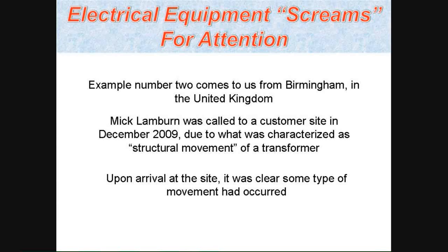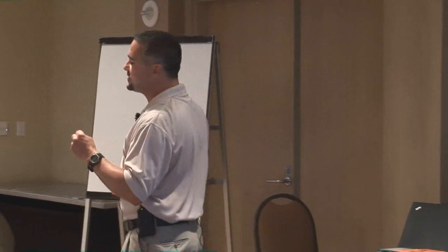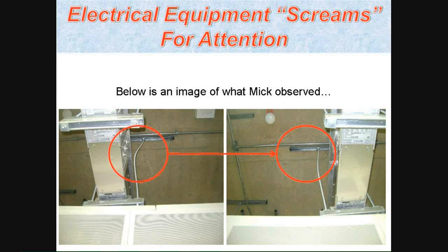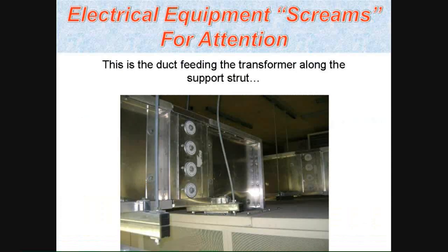And technician mine, Mick Lamburn, was at a customer site, and they asked him on another pad mount transformer just to take a listen with the ultraprobe because there was structural movement apparently taking place, causing a shift in the foundation of the transformer. And this was connected using bus duct or bus trunking on top of the unit here. And you can see that the supports holding that trunking up are bent. And this caused what? This caused the duct to get in a bind on that elbow. Well, I can assure you that's not a good situation for that.